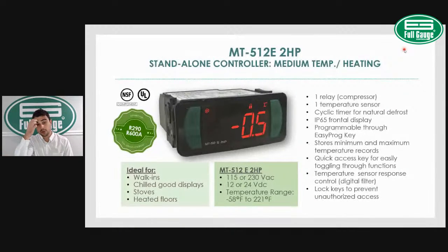I'm going to actually show you a programming device we have that is compatible with the 512 as well as with the other controls. And again, 512 is good to replace any medium temp OEM control that requires off-cycle air defrost. And when you're replacing mechanical controls, it can actually replace the thermostat plus the defrost timer and the thermometer, of course, since you're going to have a digital readout. Applications, again, any medium temp and heating systems.